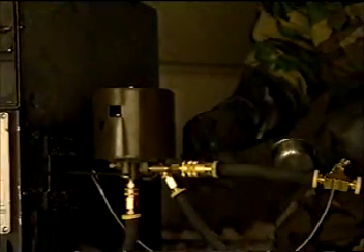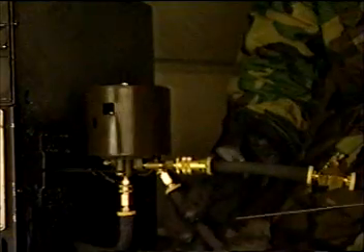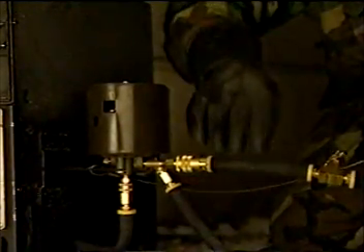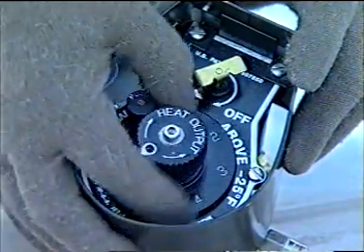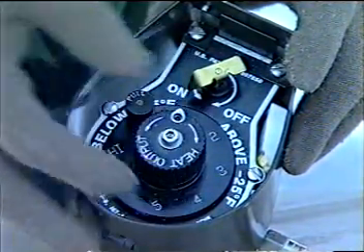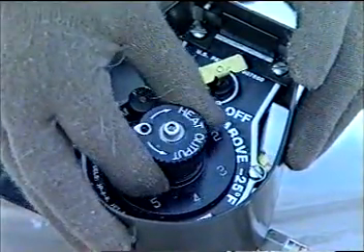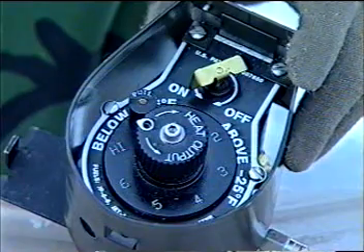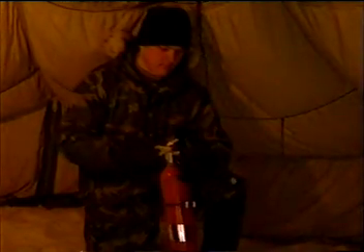In extremely cold conditions, if the firing rate on high setting is not generating sufficient heat output, tap the control valve and shake the hoses to eliminate any air that may be trapped. If output is still insufficient, turn the heater control valve to low for 5 to 10 minutes, which will heat the bottom of the burner. Then turn the control valve back to the high position. When the stove is in operation, a fully dressed, alert fire guard must be monitoring the stove at all times. This fire guard must be licensed on the stove.